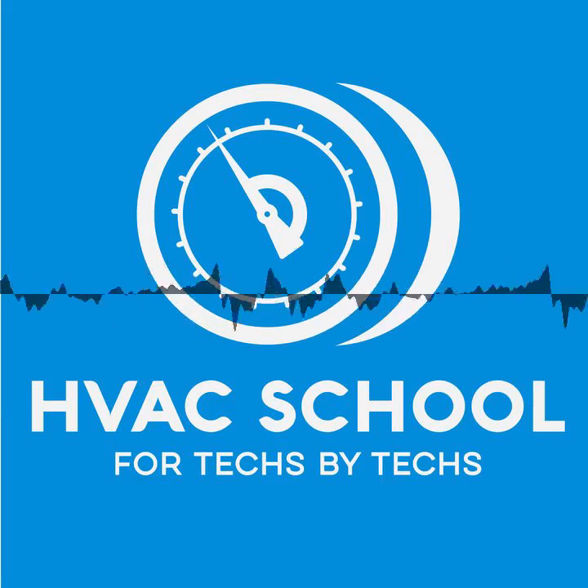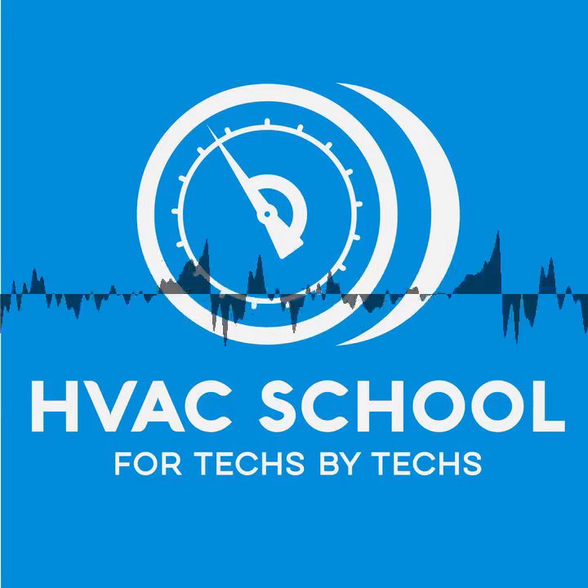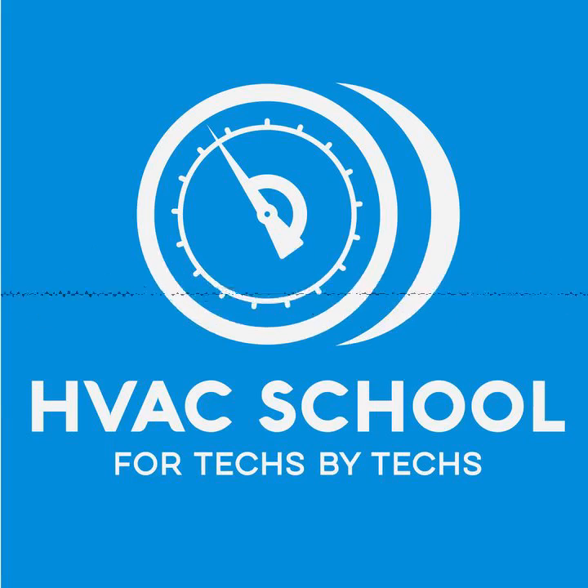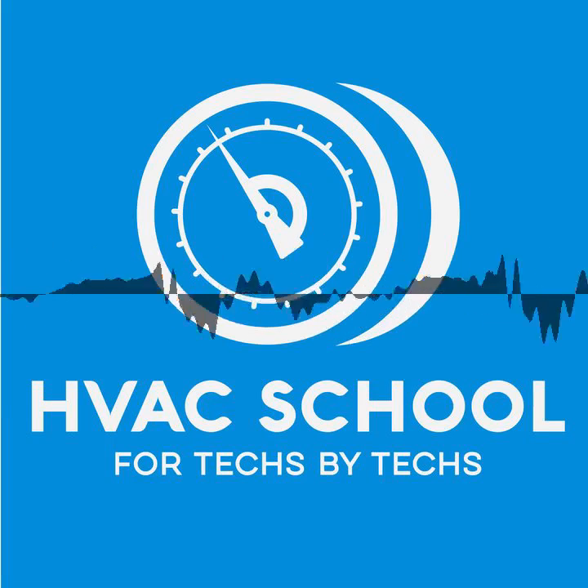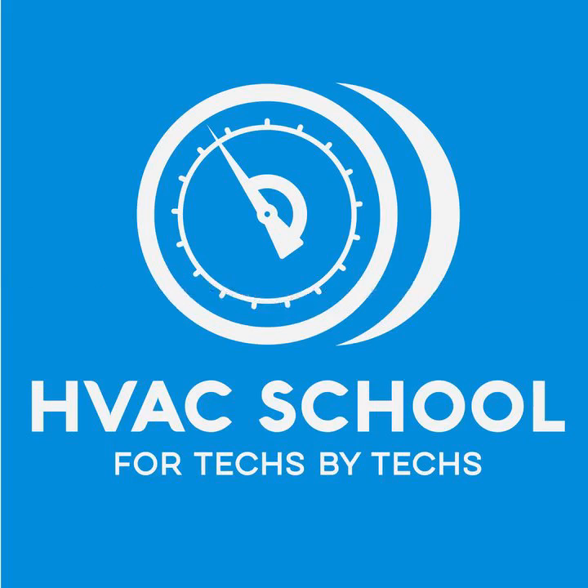So when you get into semiconductor industries and vacuum tubes and things like that, these guys hit vacuum levels that are completely unattainable by the equipment we use. They use things like turbomolecular pumps and things that probably move 10 times the amount of atmosphere that we're removing with the equipment that we use today. So I digress for a second. But if the deepest vacuum you can pull is negative 14.7 PSIG, right? That's the limitation. It's a physical limitation. You can't go deeper than that in vacuum.